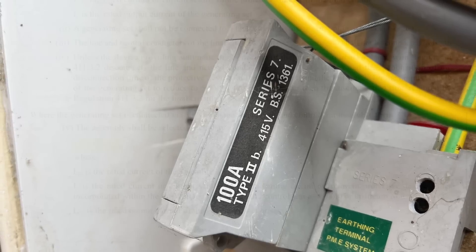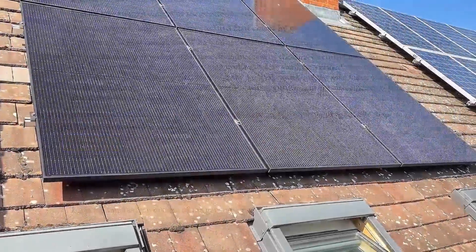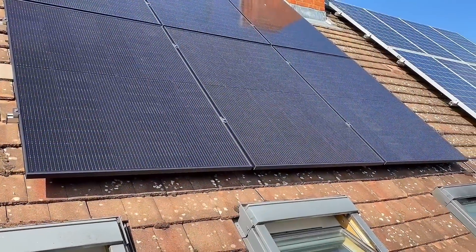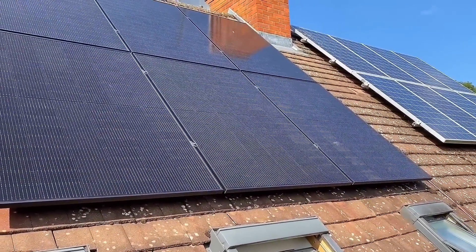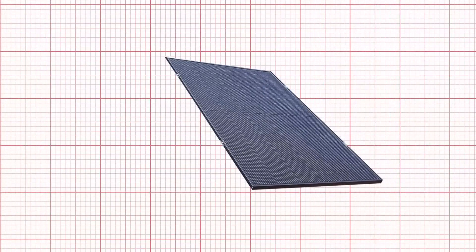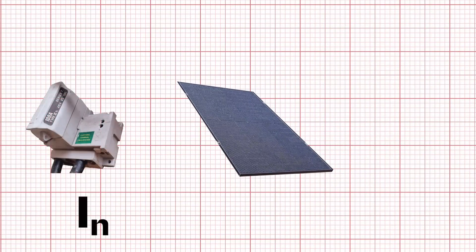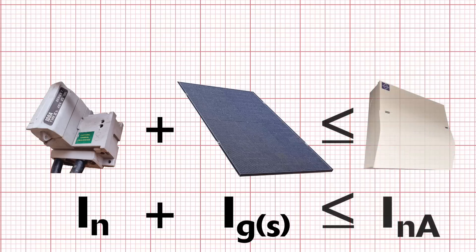So in this installation you can see it's a 100 amp fuse. Finally, IGS is how much current the generating set is capable of outputting. In a domestic setting this is likely to be 16 amps due to the export restriction placed on this kind of installation. So the regulation is telling us that when you add together the current that can be drawn through the supply and the current that can be generated by and drawn from the PV panels, it must be lower than the rated current of the assembly.